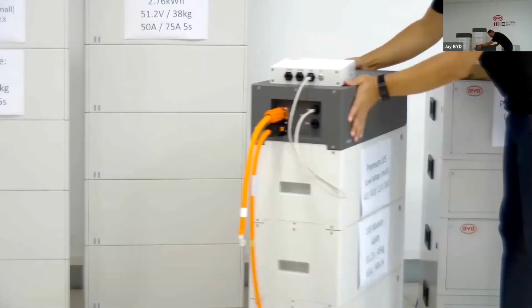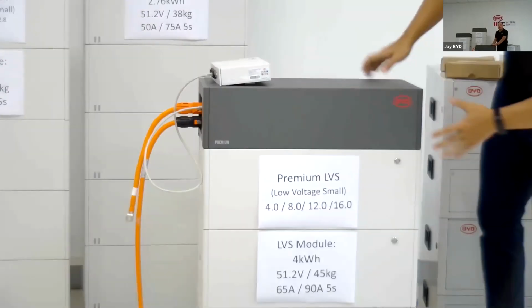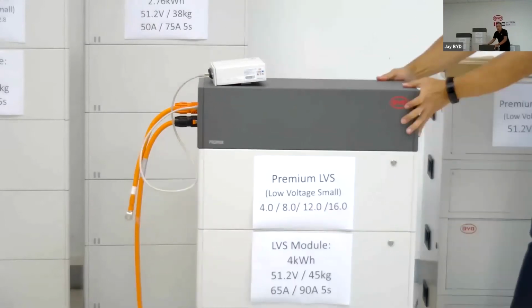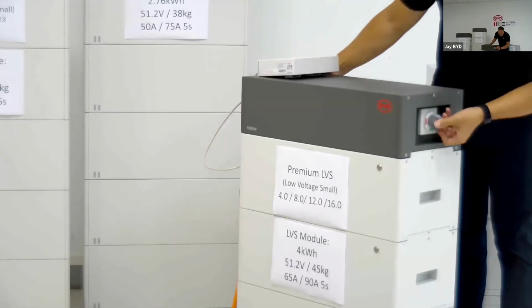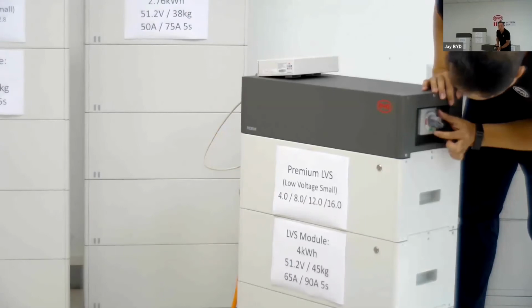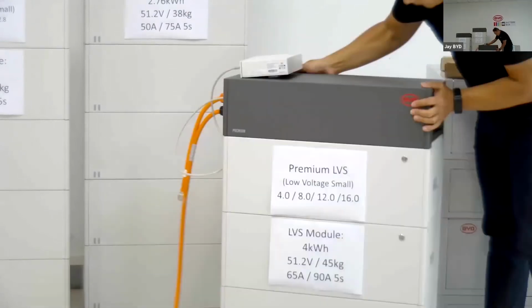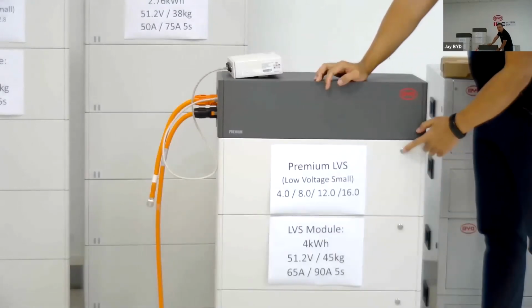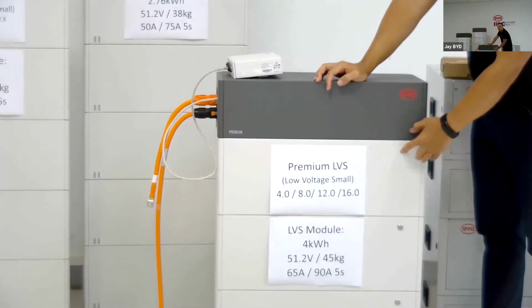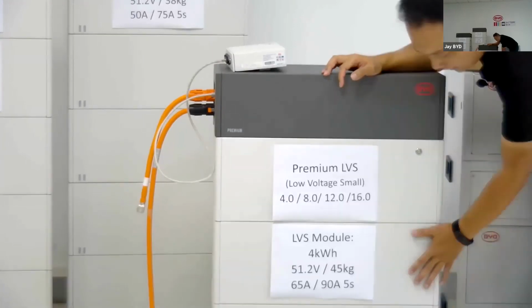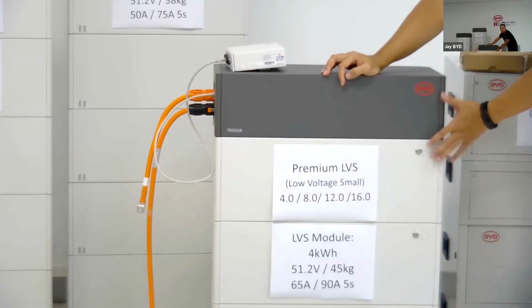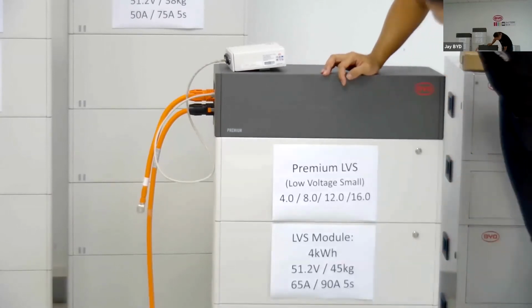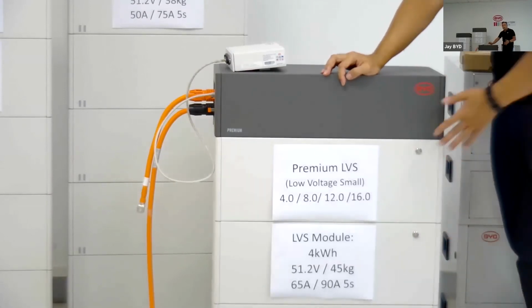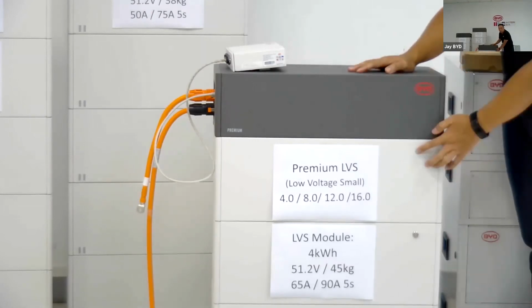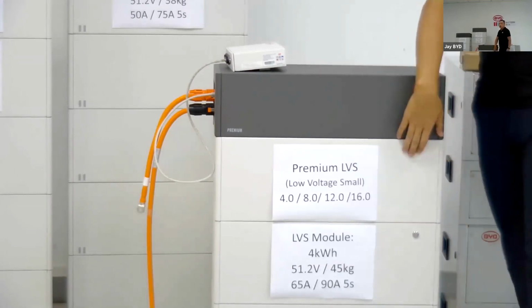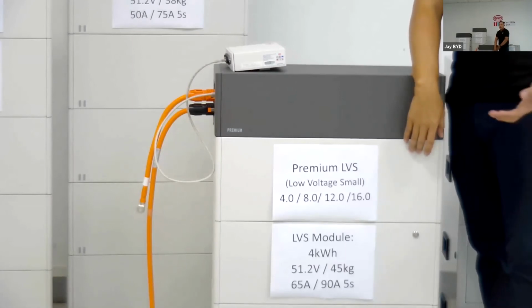Now I'm going to show how to turn on and turn off the battery. First, turn on the DC breaker, just turn it on. We've got on, trip, and off, 3 positions. Then press the top battery's on button and hold for 1 second, and the system will turn on. Don't press the other batteries' button to turn on, because the top battery has priority, right? It won't damage anything at all, it just has priority. If you have more than 1 tower, just press the top battery of the master tower, since this one has priority to get the initial address.